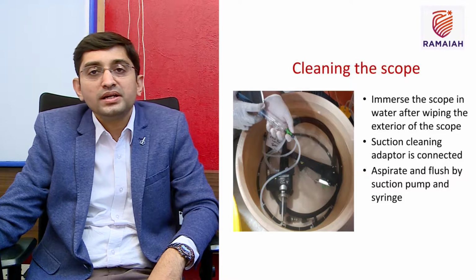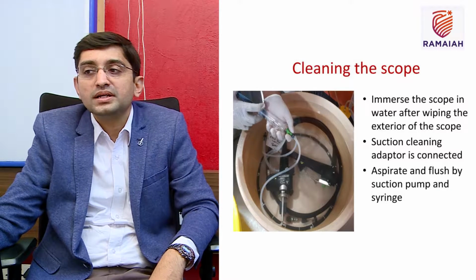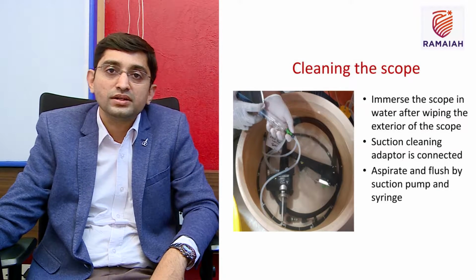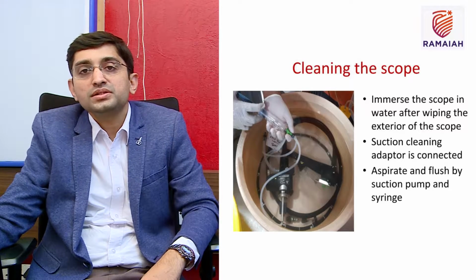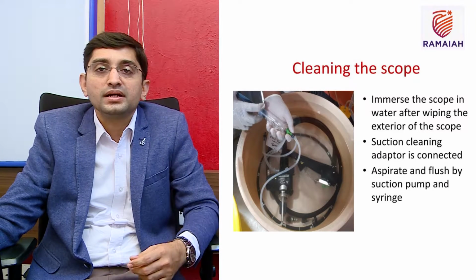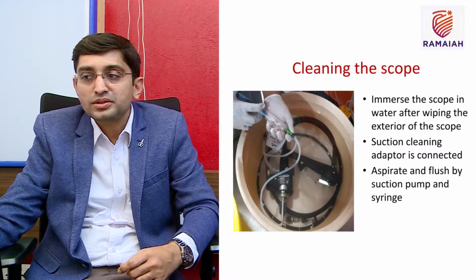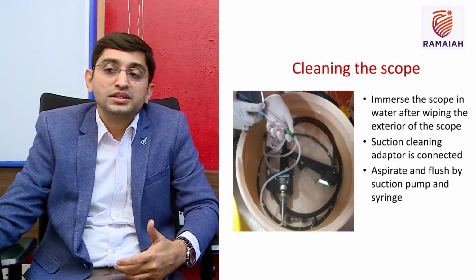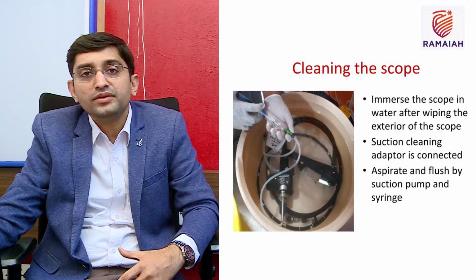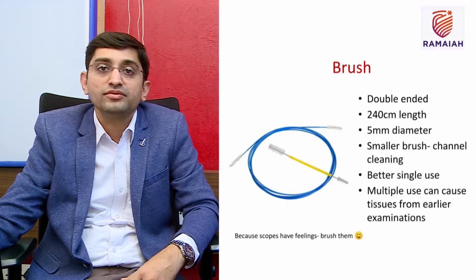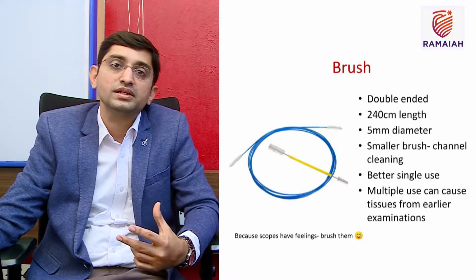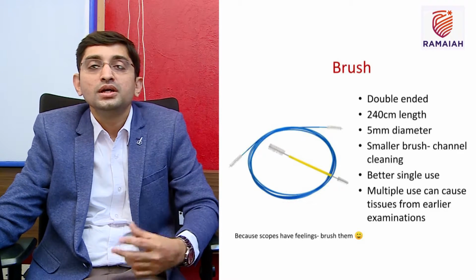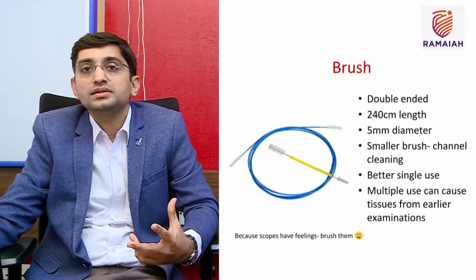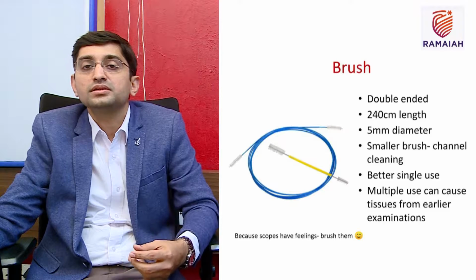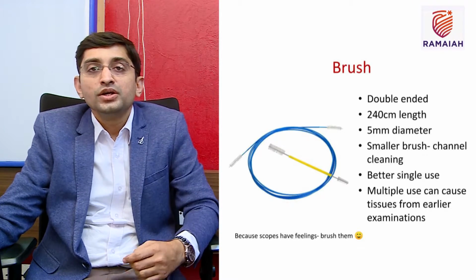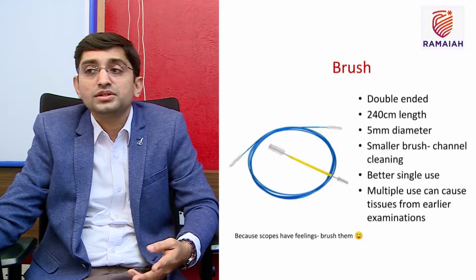Cleaning the scope: once it comes out of the patient, we should immerse the entire scope in water after wiping the exterior of the surface. Then we need to use a suction cleaning adapter, connecting it to the different ports, and then we aspirate and flush the suction pump using a syringe. Usually we tend to use a 20 ml syringe rather than a 50 ml syringe because the 20 ml syringe will give you adequate force to push. If you use a larger caliber syringe, the amount of force generated at the tip of the syringe will be much less.